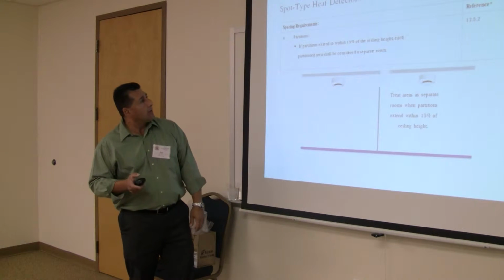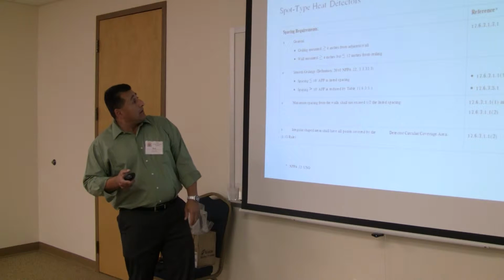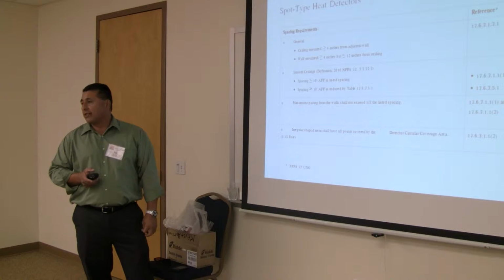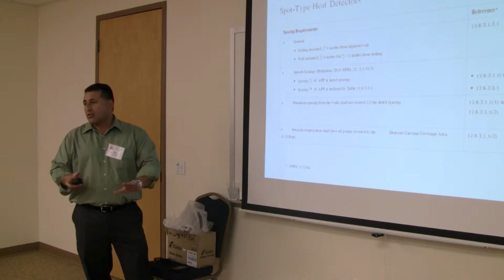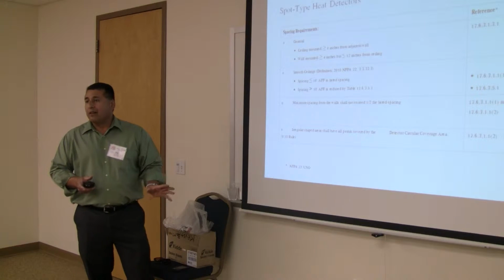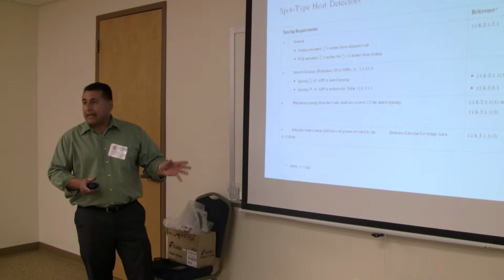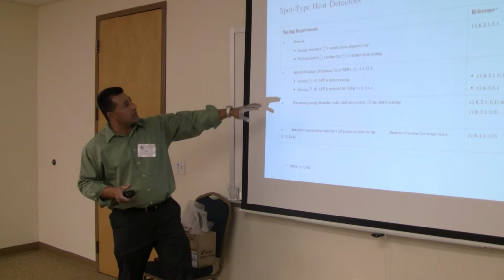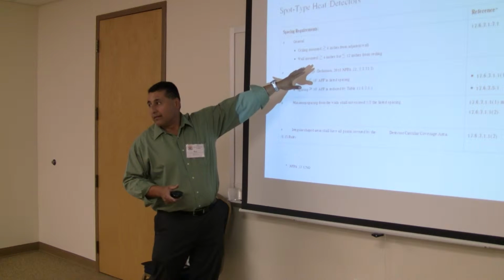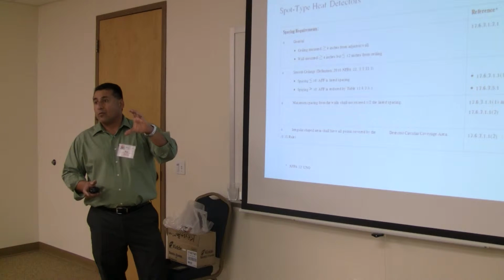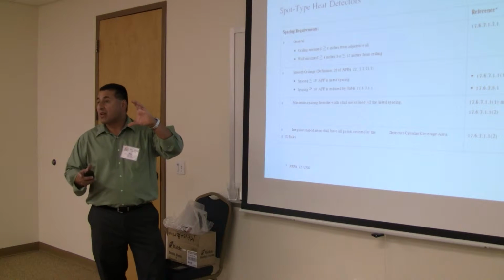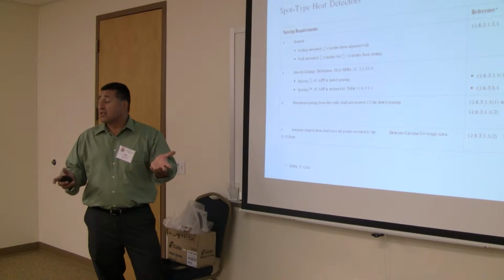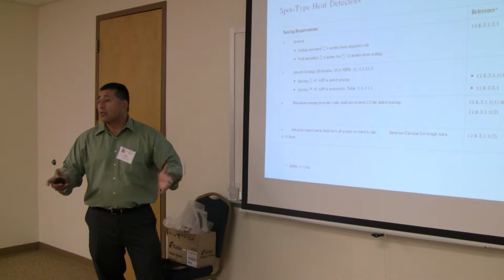All right? Let's see. Smooth ceiling. Smooth ceiling is great. If they ever have smooth ceiling, that's fantastic because you can lay it out pretty much on a two-dimensional plane. When they start doing non-smooth ceiling type coverage, you need to have that profile view because you don't know what it looks like. They've got to give you the depth because all this stuff is based on greater than or less than. Right. Okay, so you have to know what that difference is, what that difference in the ceiling soffit or whatever the case may be as far as the beams, to see if you need to actually put coverage in the pockets or if you can do smooth ceiling and just put them every so often and have regular coverage.